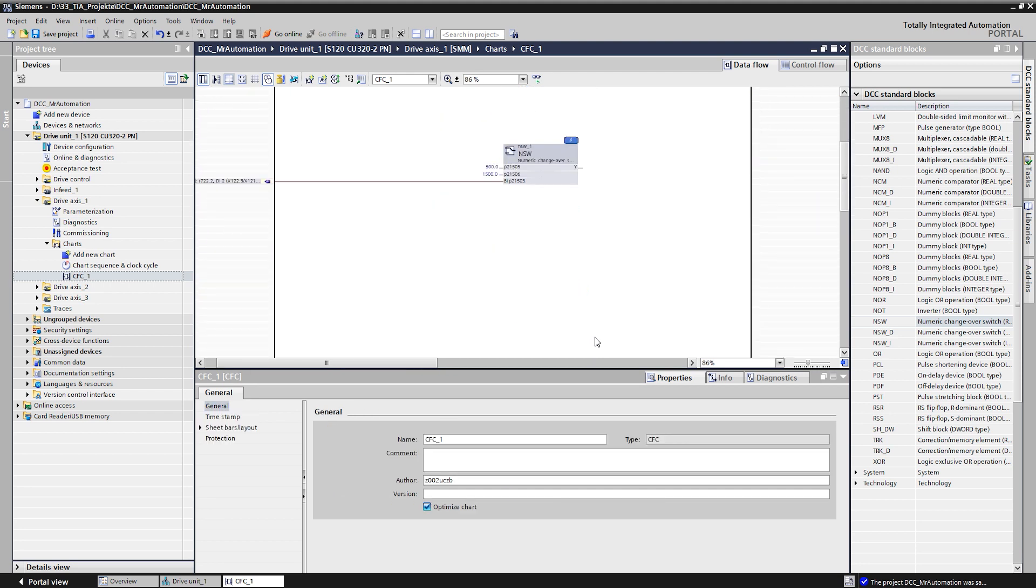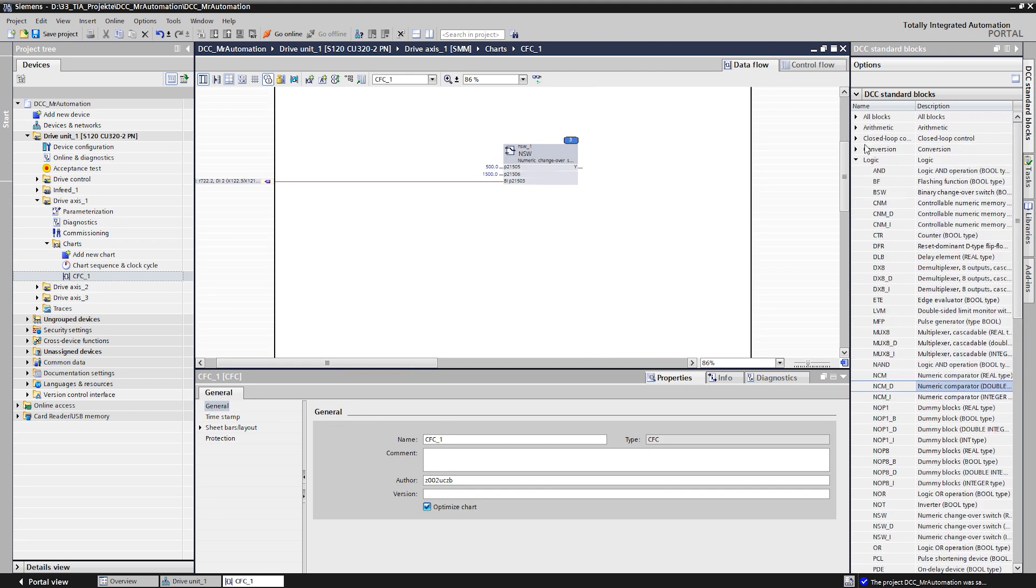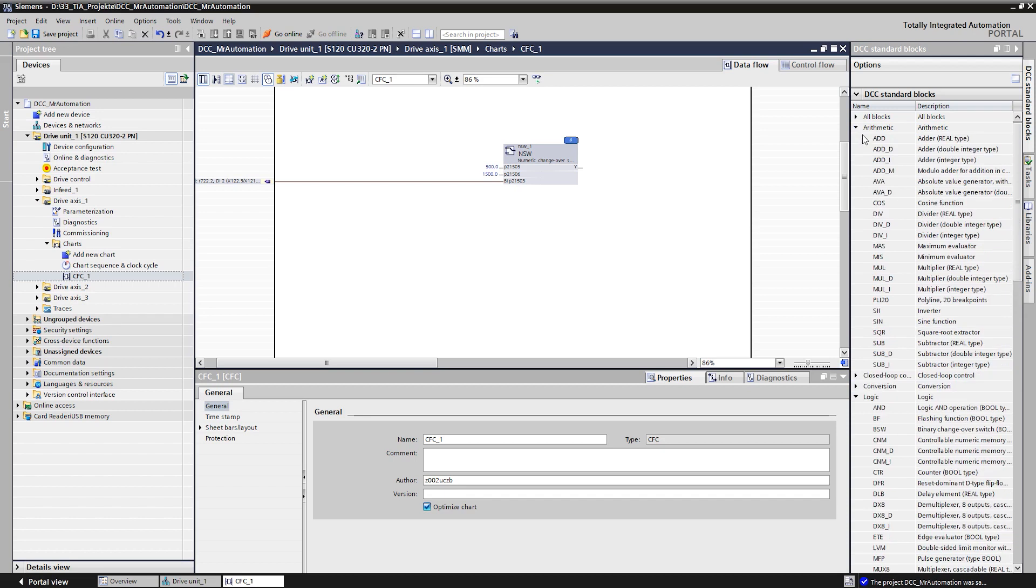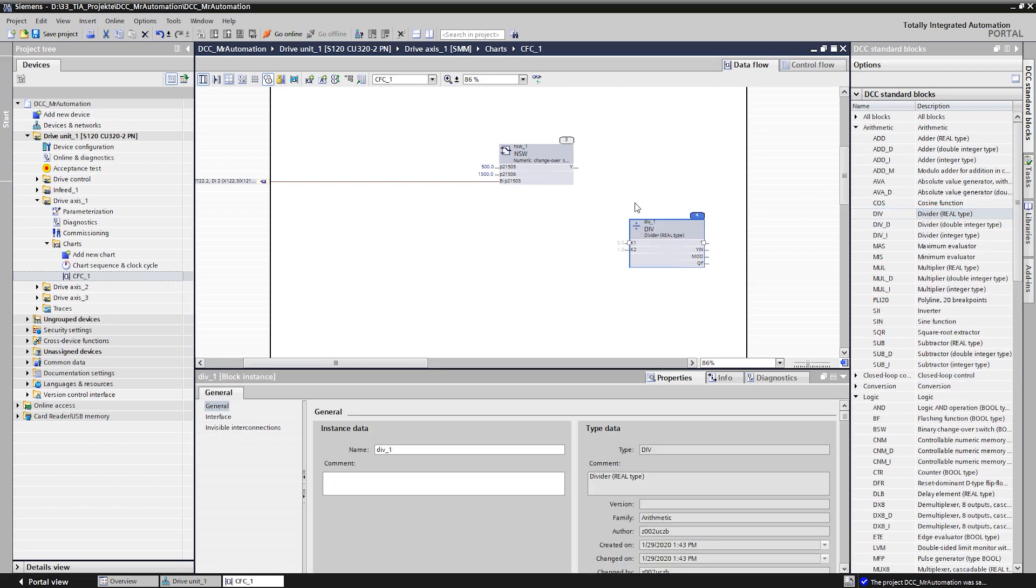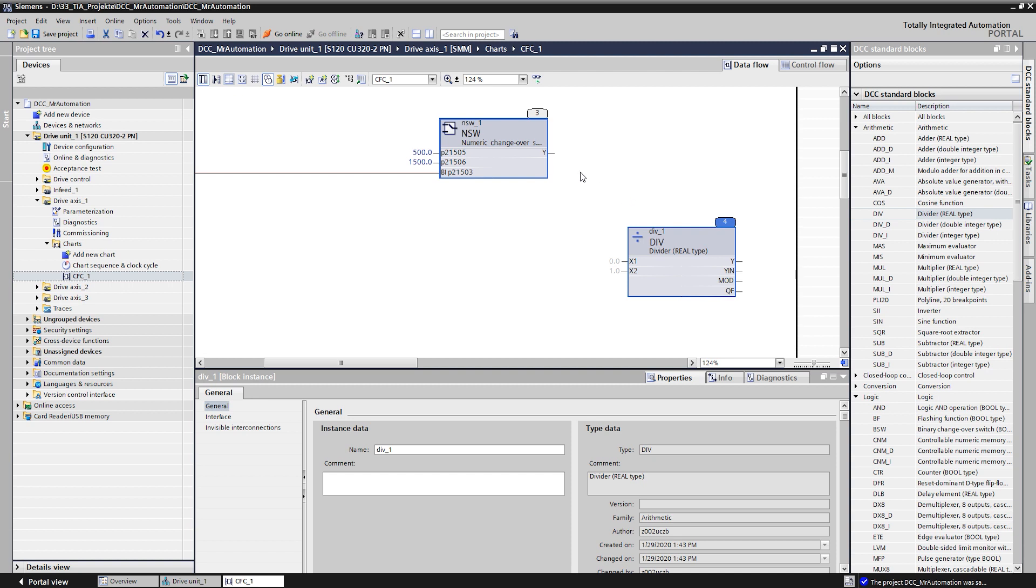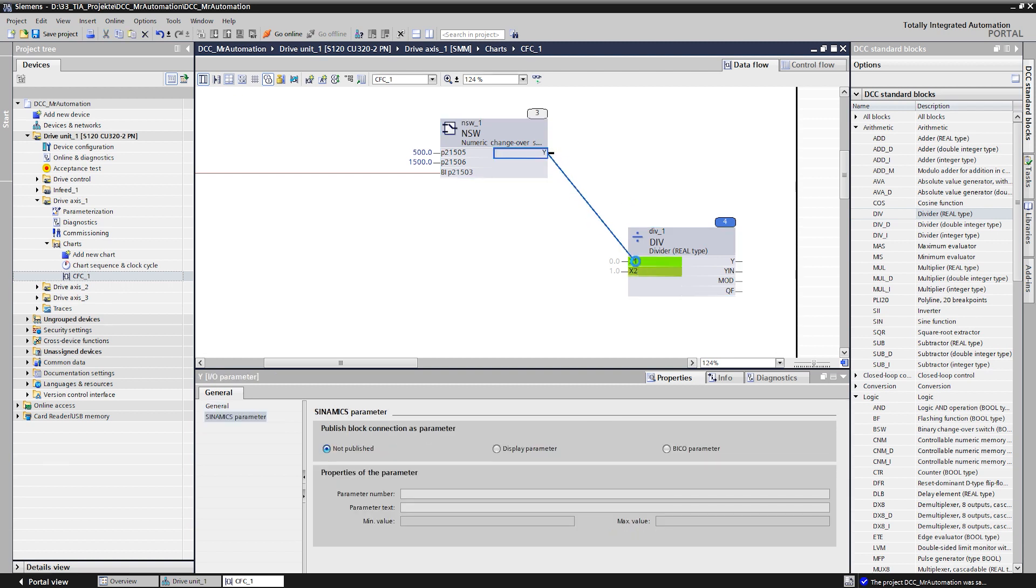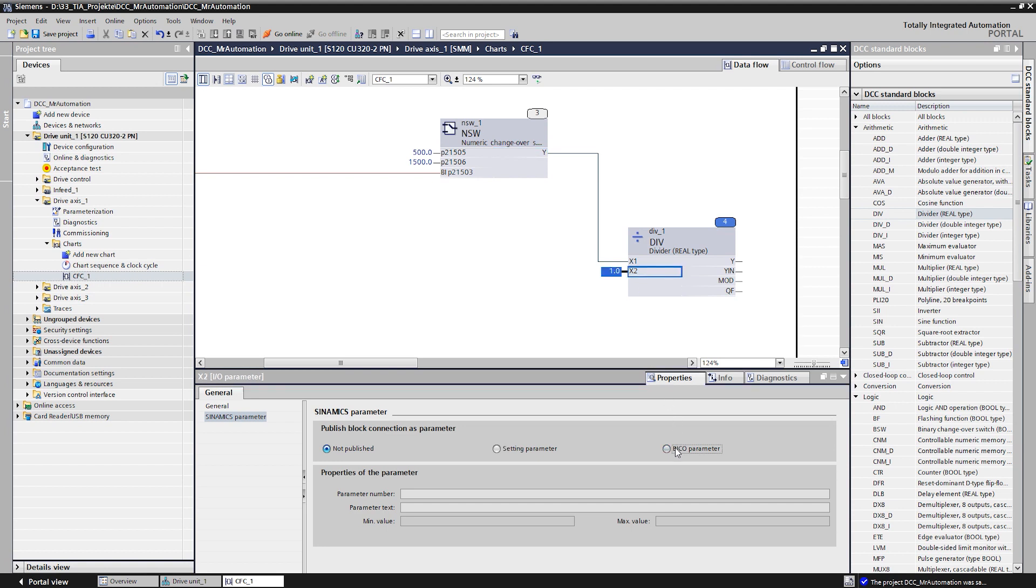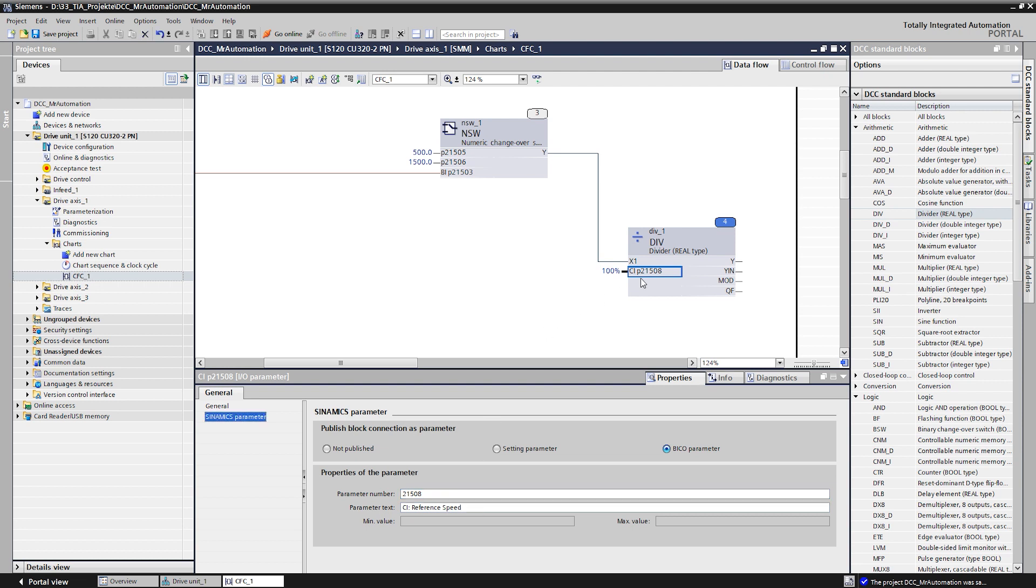So, we insert a dividing module from the arithmetic folder and connect the output of the numeric switch to the input for the dividend. The reference value for the speed is available as parameter of the basic system. We publish the divisor input of the module as BCO parameter and connect the corresponding reference value from parameter p2000.